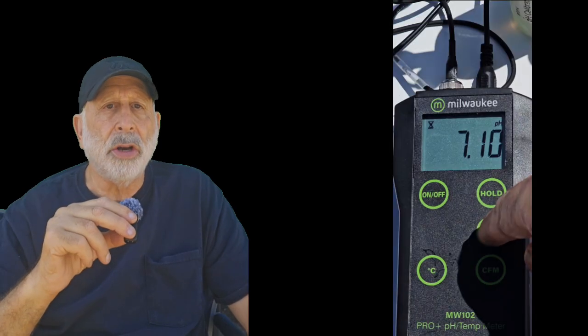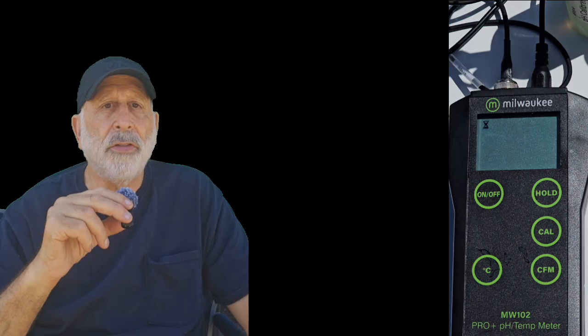For a 2-point calibration, the first buffer should always be 7.01. This is the first calibration point, often called the offset point, where you're telling the meter that this is correct. Now measure everything from here. 7.01 is your starting point.